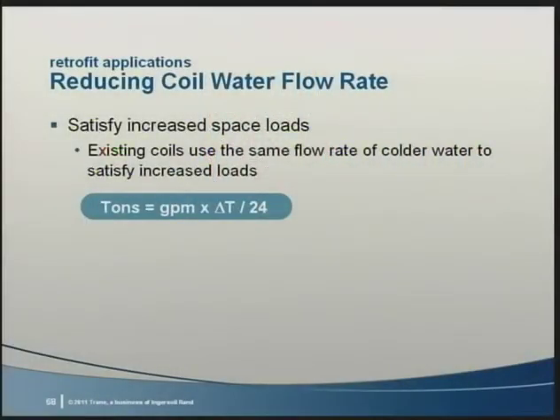Let's say there's an existing space, such as an operating room, where the space requirements have changed and they need to satisfy more load. By sending the existing coils the same amount of colder water, more load can be satisfied in the existing space. Simply reselect the coil with the same flow rate, but at a lower entering water temperature. You'll see the effect on leaving air conditions and an increase in coil capacity.